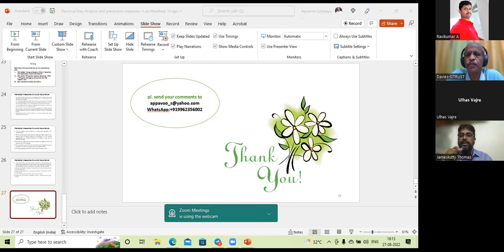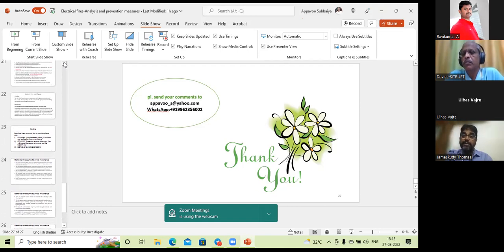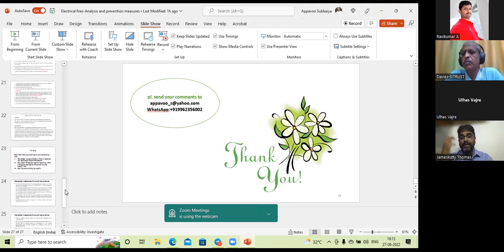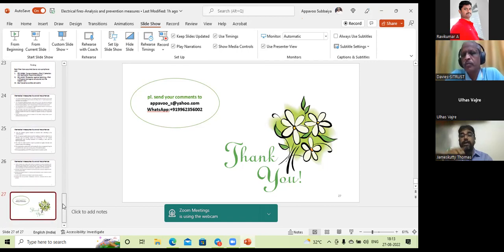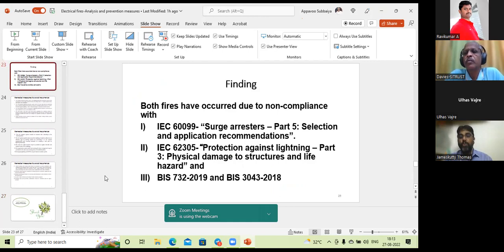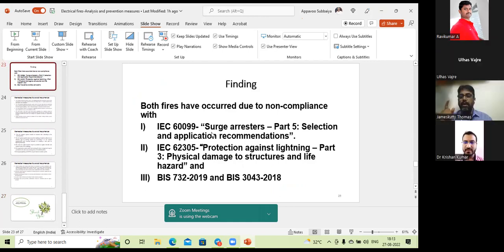In the case Appavoo sir explained, the early streamer emission rod attracted the lightning, or it caused the lightning to affect the installation, but it was not properly dissipated. That was the reason. Earthing was not proper, that is the only cause for the fire. Only that much. Thank you.